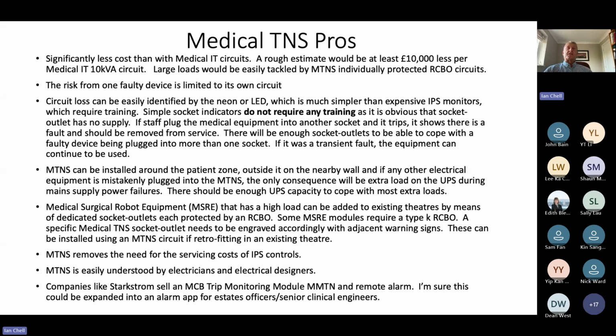So large loads are easily tackled by MTNS by individually protected RCBO circuits. The risk from one faulty device is limited to its own circuit, okay? Exactly the same as with medical IT, except you don't get the alarm. But remember that we're not getting the faults these days, that patient limit current is limited by the device, not the circuits. So also, compared to medical IT, medical TNS has a simple red LED in the socket, which is much simpler than expensive monitors, which require training. There is no training required for a simple lamp on a socket. Everybody will understand it compared to the alarm in a Group 2 environment, okay?